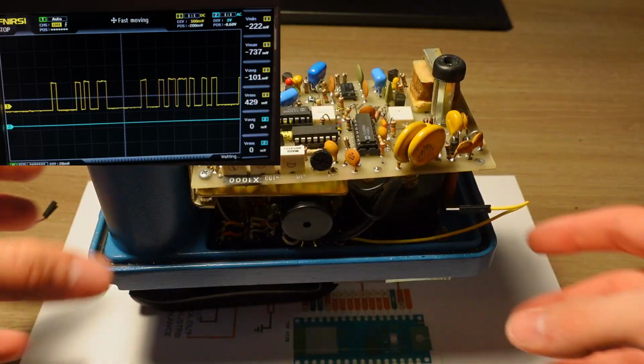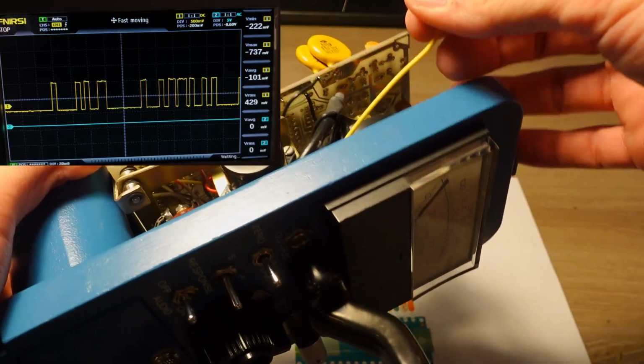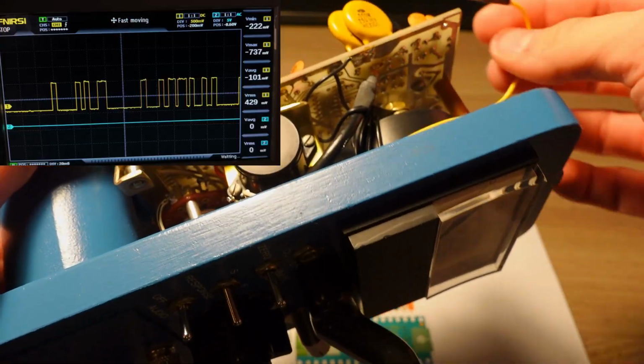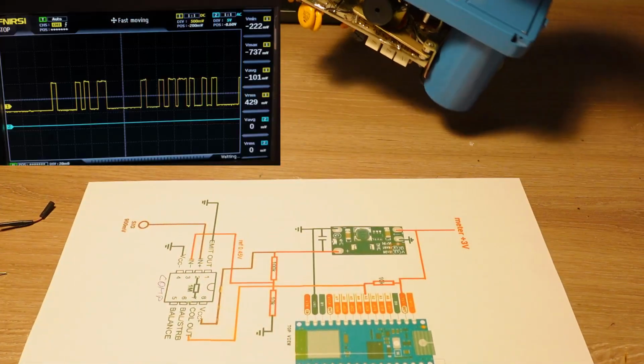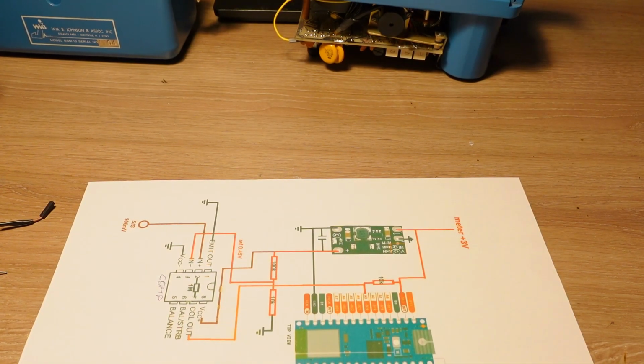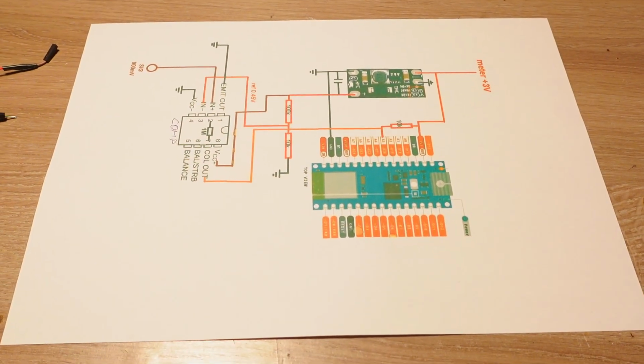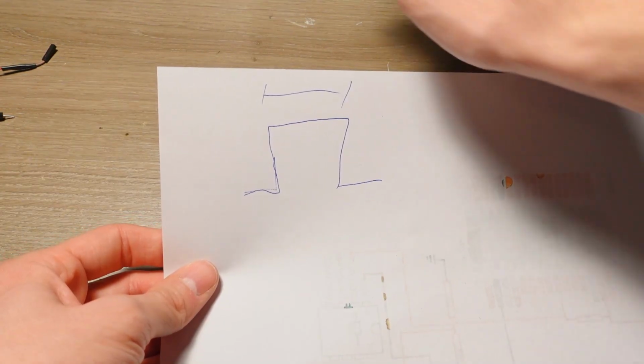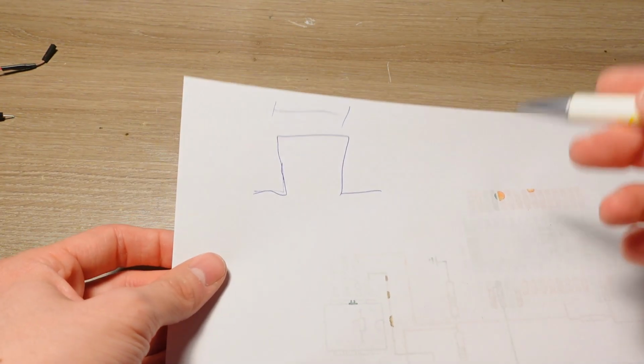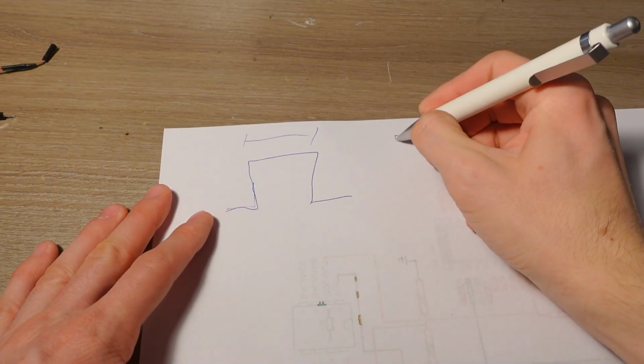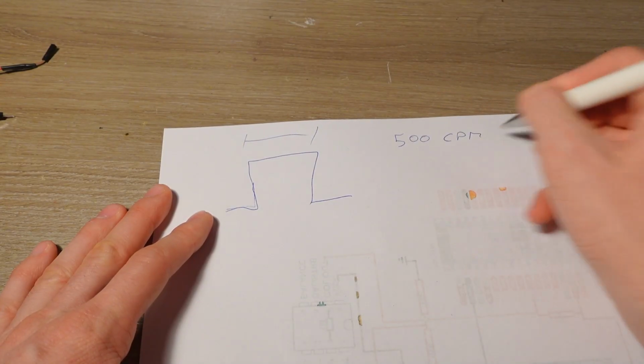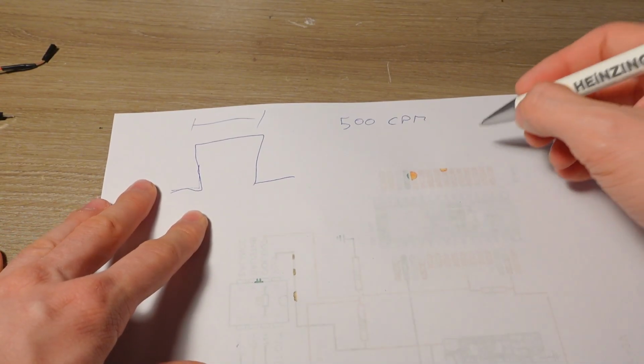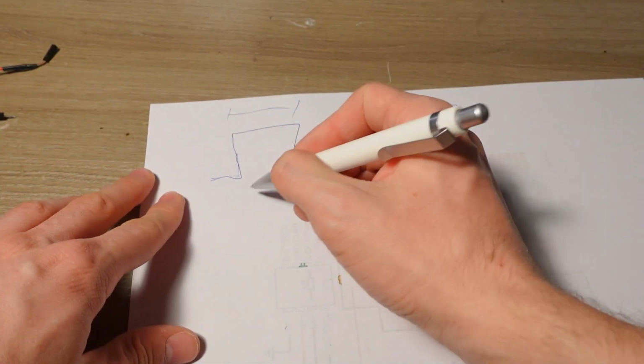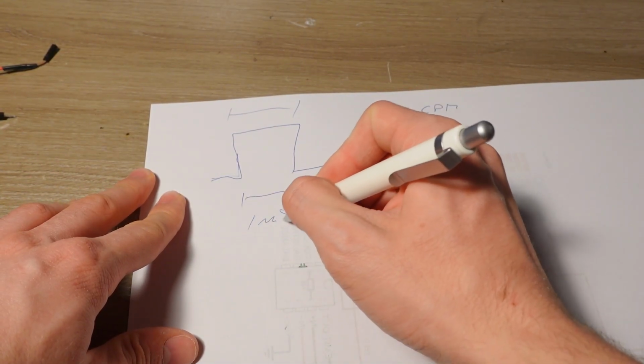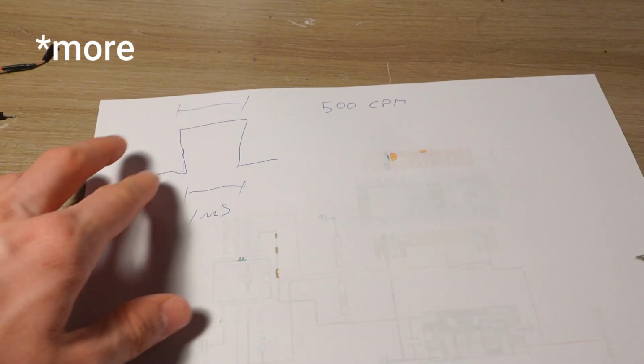But if we tap correctly on the board with just one cable, we can intercept that square pulse that is created inside of the electronics of the counter for every radiation event that it measures. If we are, for example, on the 1x scale, our maximum rate will be 500 counts per minute, and so the pulses can be very long in time, for example 1 millisecond or a bit less.